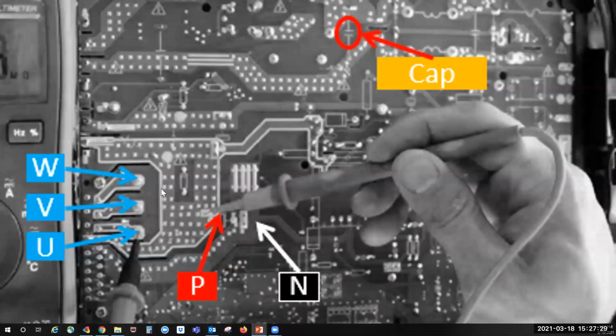Here's another good location. You've got the U, V and W, the P and the N. Up here is a small, different capacitor. I prefer to find the larger ones, they're just easier to deal with. You do want to make certain your unit's been off for 10 minutes, which allows the capacitors to discharge. Once again, we're checking for resistance, not a specific amount, and these do fall within the megaohm range. You'll put your black probe on the U, V and W on the IPM and your red on the positive, and you're just looking for a consistent resistance.